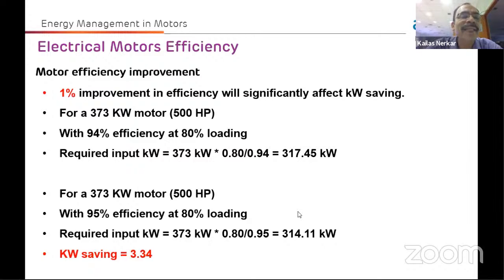Here is a simple example: for a 373 kilowatt, 500 HP motor with 94% efficiency at 80% loading, the required input is 317.45 kilowatt. If the same motor with 95% efficiency is used at the same loading, the consumption is 314.11 kilowatt. That means you can save 3.34 kilowatt.